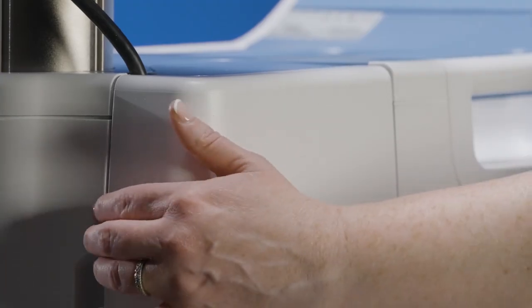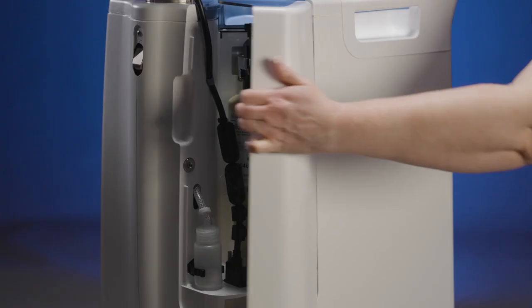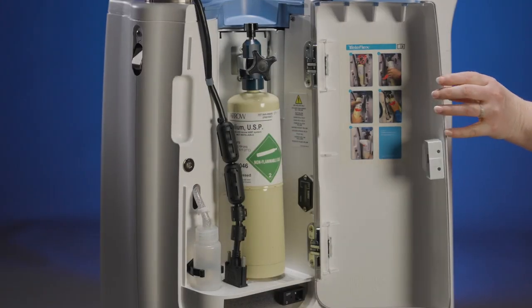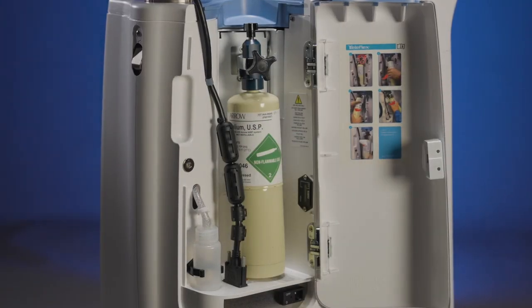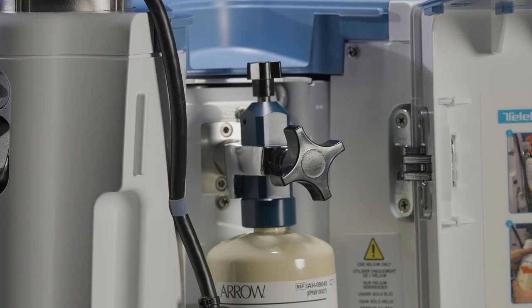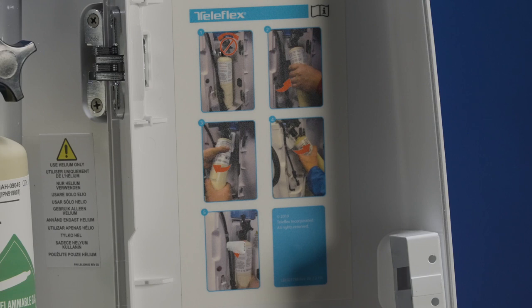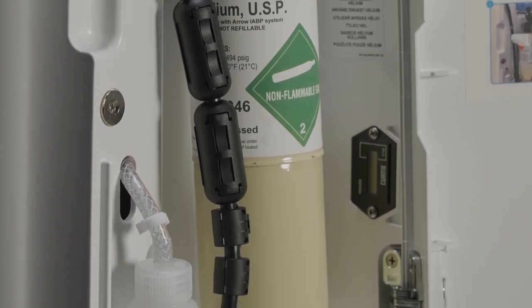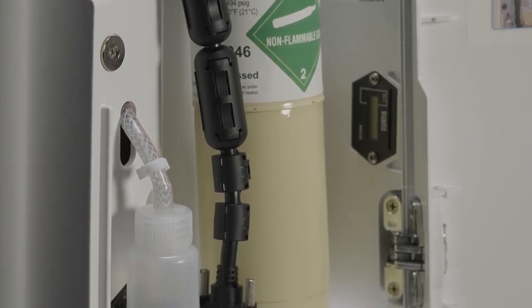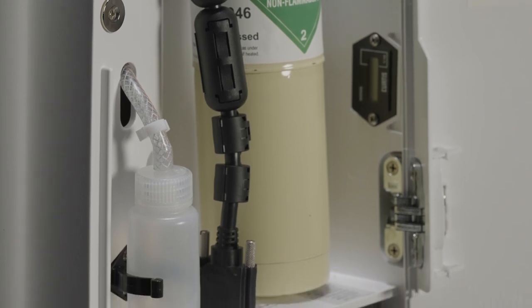The compartment located on the left rear of the pneumatic drive module houses a 500 psi disposable or 2000 psi refillable helium tank. The AC3 Optimus IABP also has a thermoelectric baffle system to condense and remove moisture from the pneumatic lines. The liquid drains into a condensation collection bottle located in the helium storage compartment.